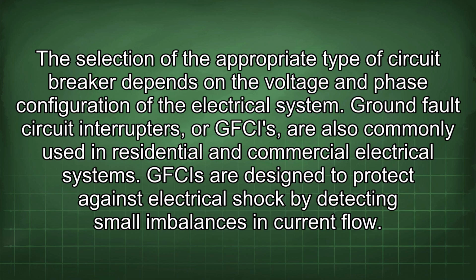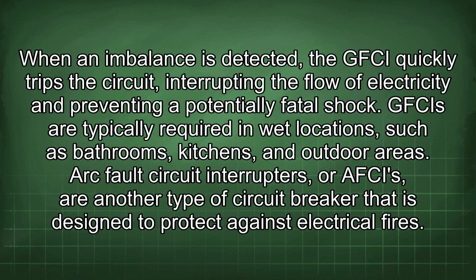Ground fault circuit interrupters, or GFCIs, are also commonly used in residential and commercial electrical systems. GFCIs are designed to protect against electrical shock by detecting small imbalances in current flow. When an imbalance is detected, the GFCI quickly trips the circuit, interrupting the flow of electricity and preventing a potentially fatal shock. GFCIs are typically required in wet locations, such as bathrooms, kitchens, and outdoor areas.